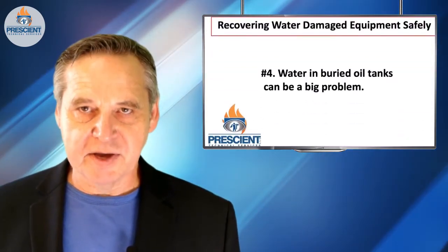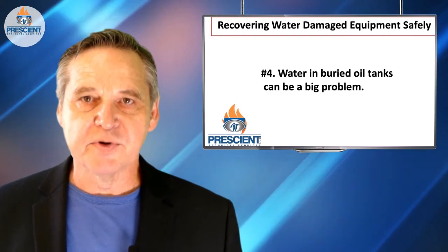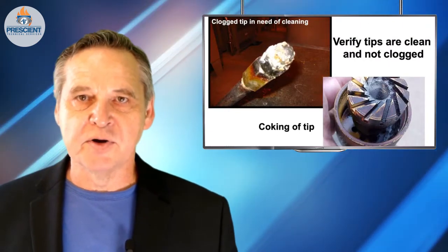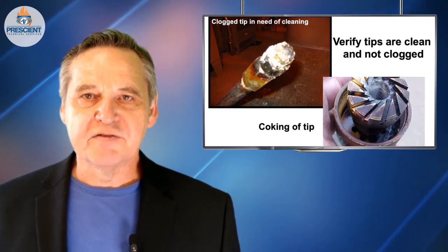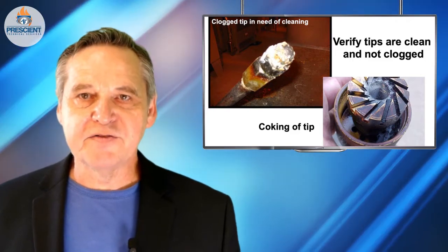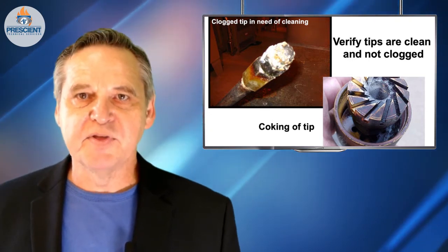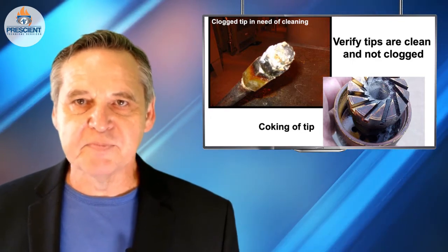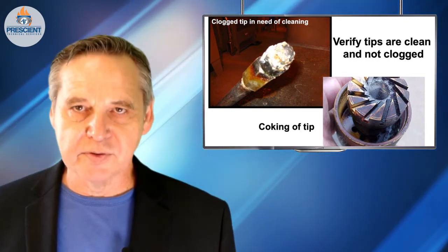If you've got buried fuel tanks containing fuel oil, maybe as a backup fuel, and you've got water mixed in with the fuel oil, most likely you're into a salvage effort to find someone who will take that material. If you can drain off some of the water, it's likely you're going to need to dose that fuel oil with biocides as well. There are many bacteria which like to consume hydrocarbons and oil. If you start to pump this through your system, you'll gum everything up, including strainers and burner tips — it'll just be a mess. So there's got to be very careful attention given to fuel oils.